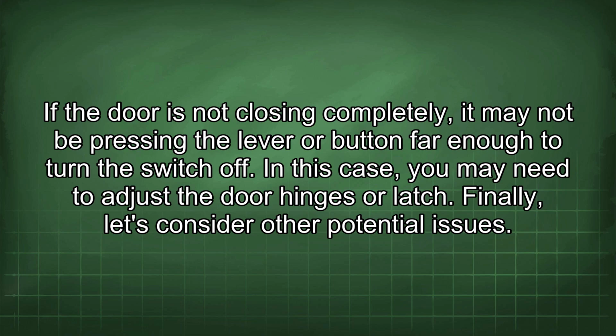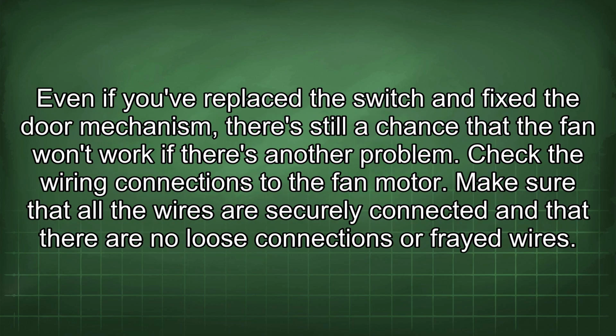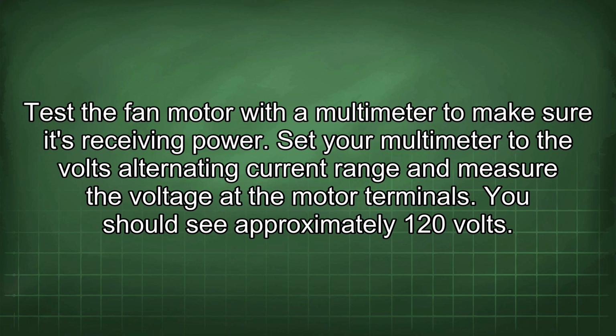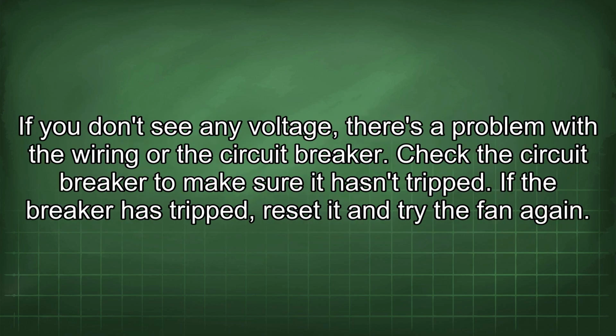Finally, let's consider other potential issues. Even if you've replaced the switch and fixed the door mechanism, there's still a chance that the fan won't work if there's another problem. Check the wiring connections to the fan motor. Make sure that all the wires are securely connected and that there are no loose connections or frayed wires. Test the fan motor with a multimeter to make sure it's receiving power. Set your multimeter to the volts alternating current range and measure the voltage at the motor terminals. You should see approximately 120 volts. If you don't see any voltage, there's a problem with the wiring or the circuit breaker.